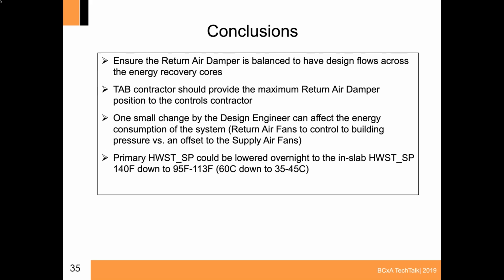So the conclusions of this is that you need to ensure that the return air damper is balanced to have the design flows across the energy recovery cores, or you're just not going to get it. The TAB contractor needs to provide that maximum value that the damper should be open when the cores are active, so i.e. somewhere around 80% or lower. The return fans would also need to have better control, not to the building static. And how one small change made by the design engineer can affect the energy consumption of the system when that return fan went from being an offset from the supply fan to being controlled to building pressure.